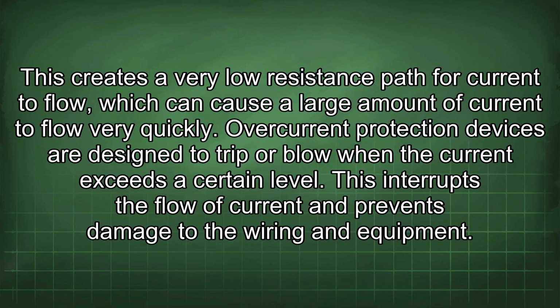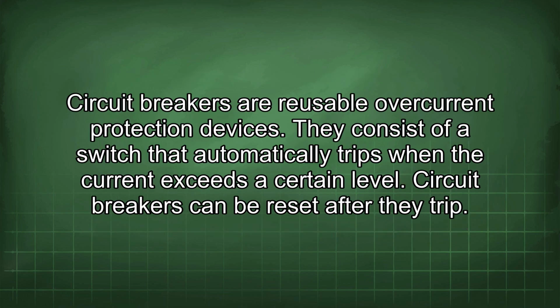This creates a very low resistance path for current to flow, which can cause a large amount of current to flow very quickly. Overcurrent protection devices are designed to trip or blow when the current exceeds a certain level. This interrupts the flow of current and prevents damage to the wiring and equipment. Circuit breakers are reusable overcurrent protection devices. They consist of a switch that automatically trips when the current exceeds a certain level. Circuit breakers can be reset after they trip.